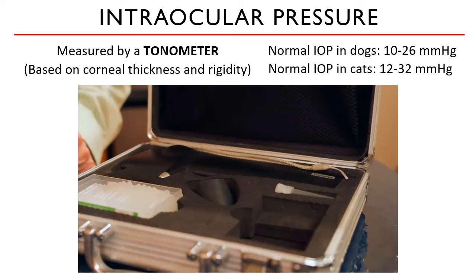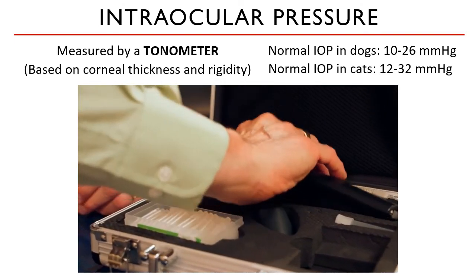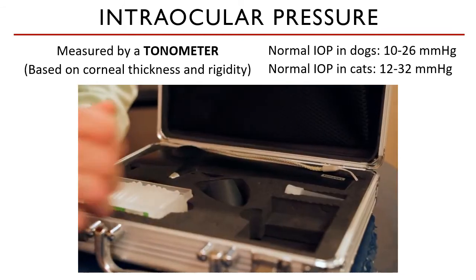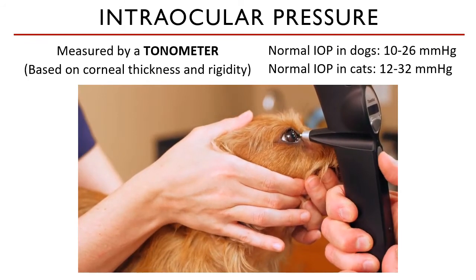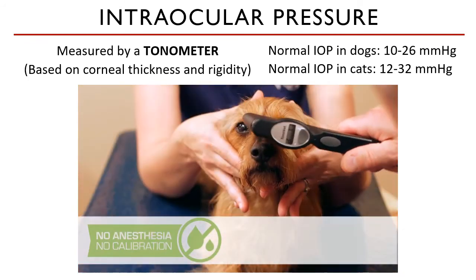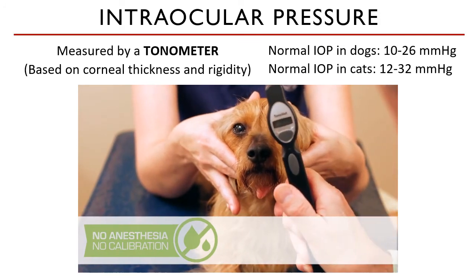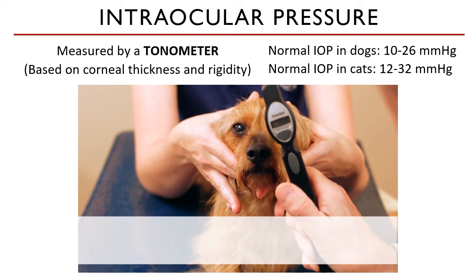Let's see how a tonometer works. Intraocular pressure is measured with a rebound principle — a lightweight sterile probe is inserted into the instrument and will gently make contact with the cornea. Tonometry with a TonoVet is a very quick process; it requires no anesthetic and should cause no discomfort, and it will not place excessive pressure on the eye. After three to five probes, the machine will give you a value of the IOP in that eye.